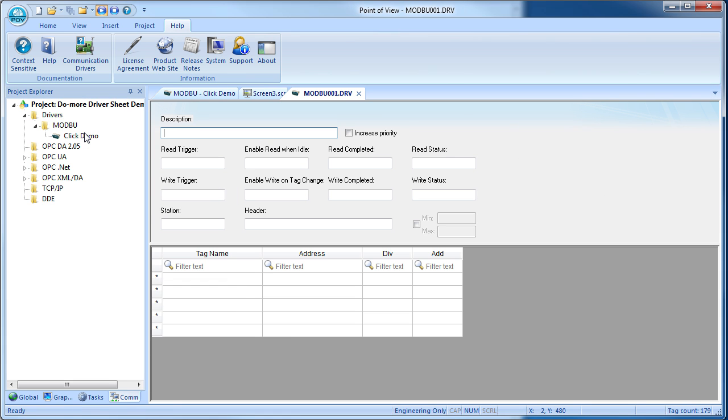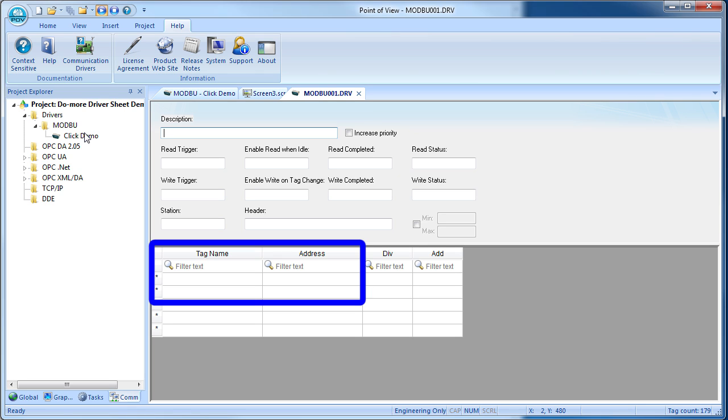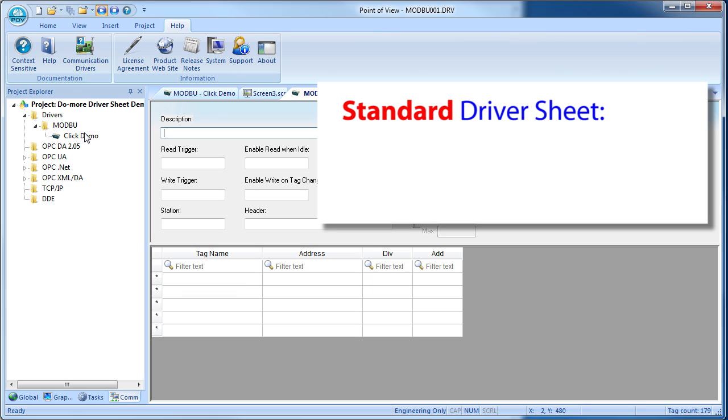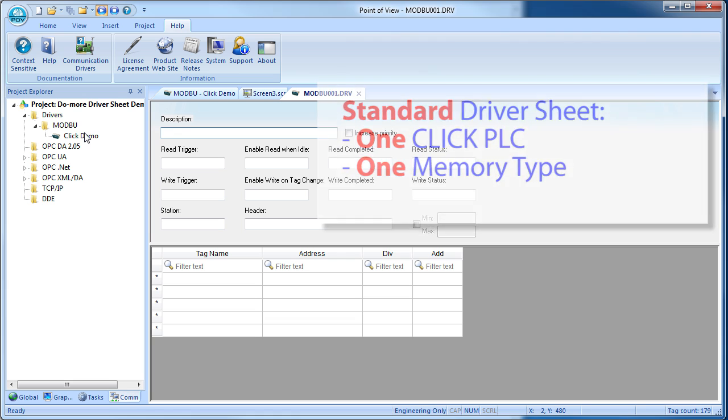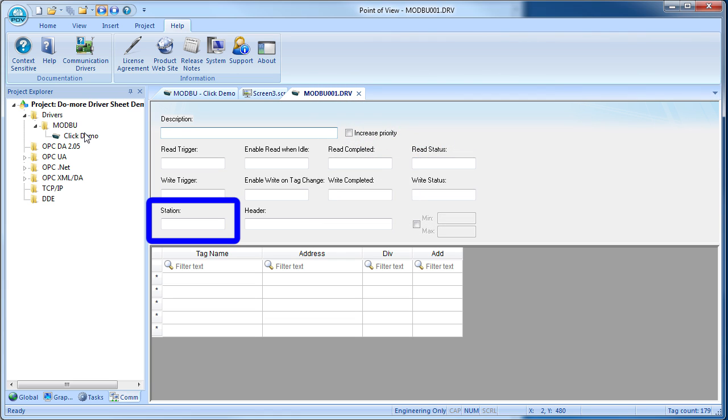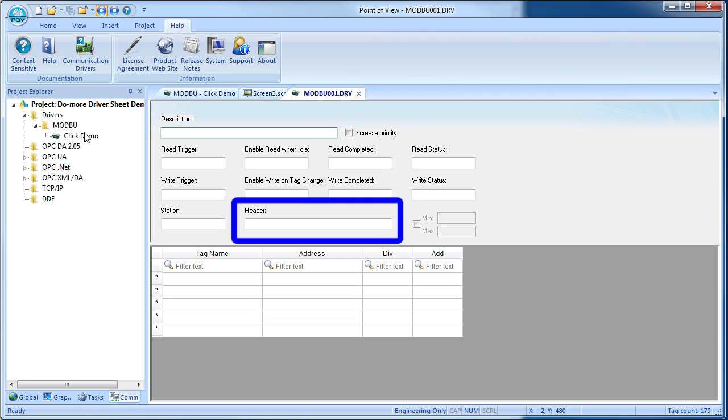Once you have your Modbus driver in place, just right-click on the folder to insert a standard driver sheet. It is the exact same thing where you fill in the local tag name and the address to go fetch it from on the Click, but this kind of driver sheet can only talk to one Click and one memory type on that Click. So you set the Click's node address here and the memory type here since they are common for every entry in the table.